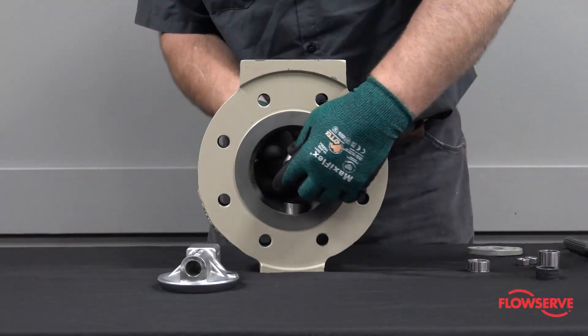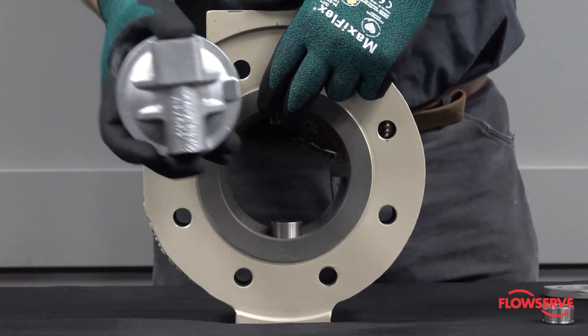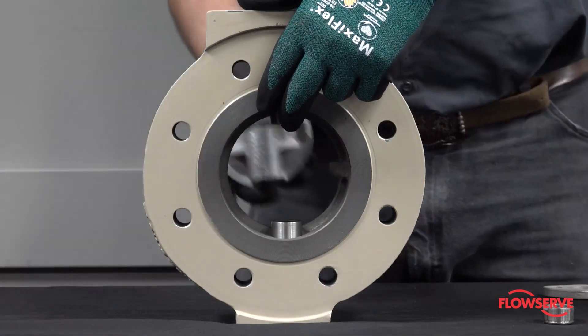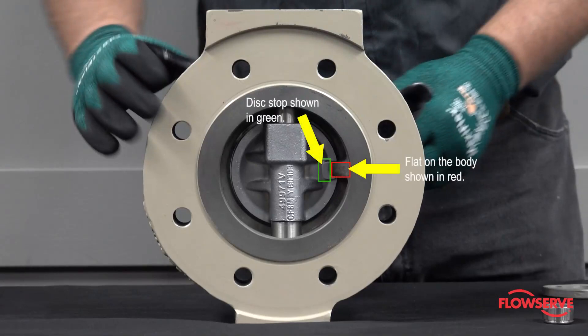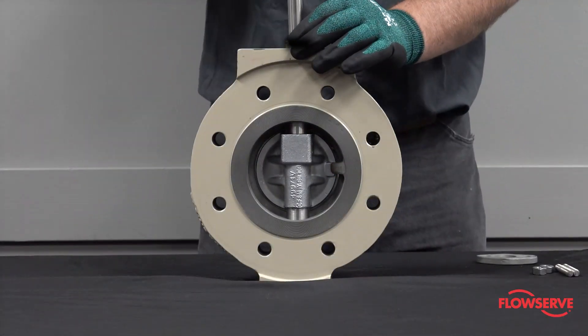Insert new shaft bearings into the body. Place the disc into the body, making sure the disc stop is lined up with the flat on the body. Carefully install the shaft.